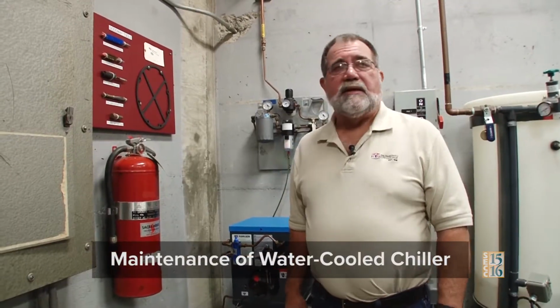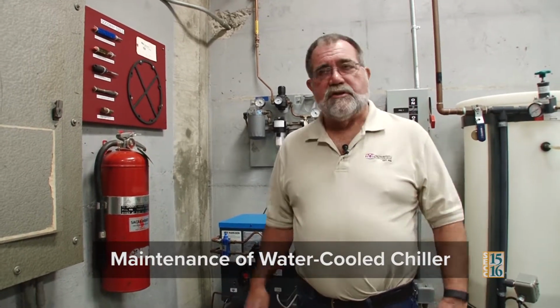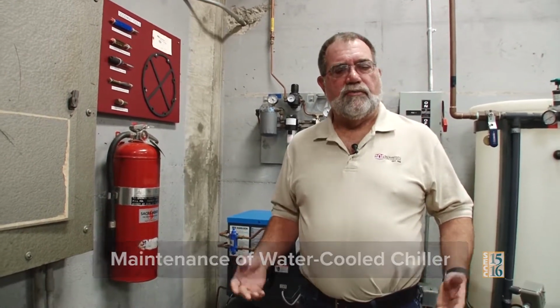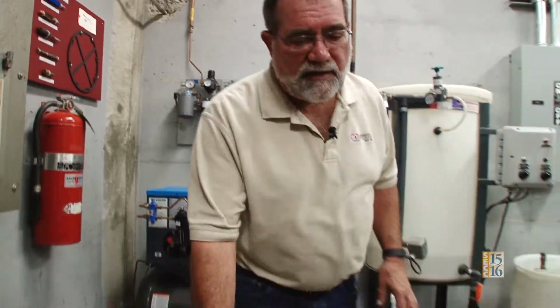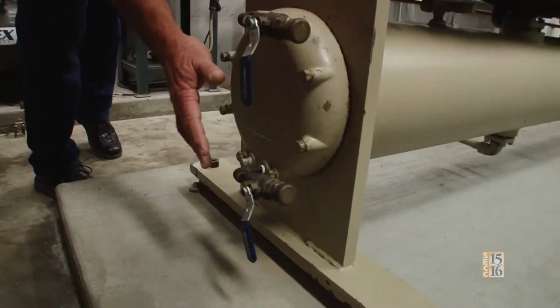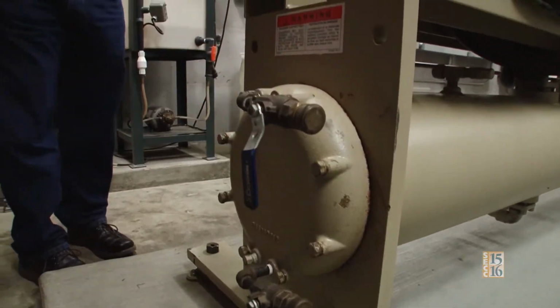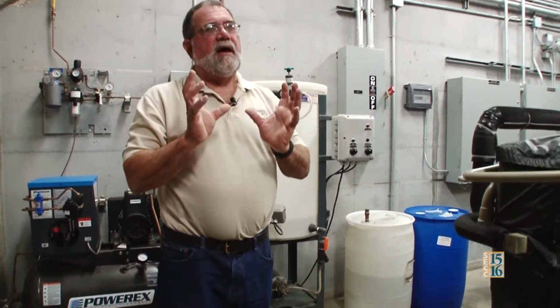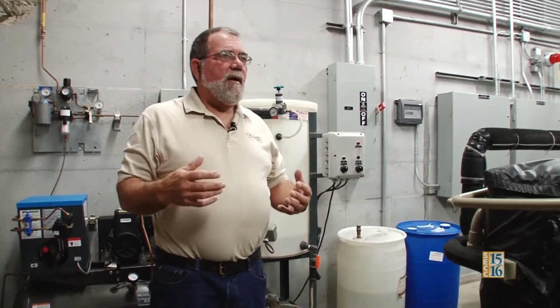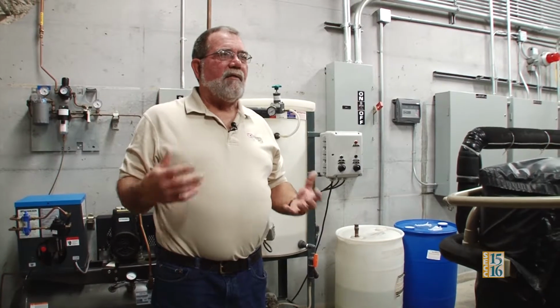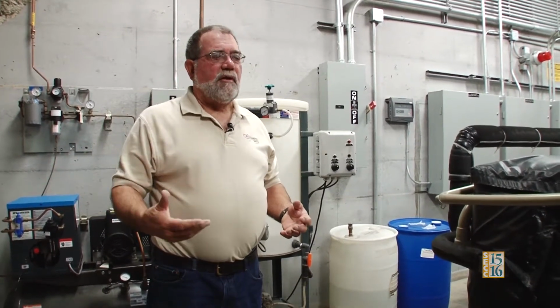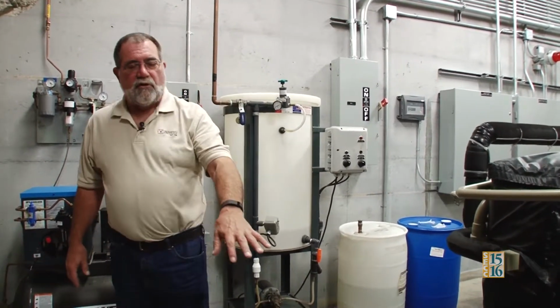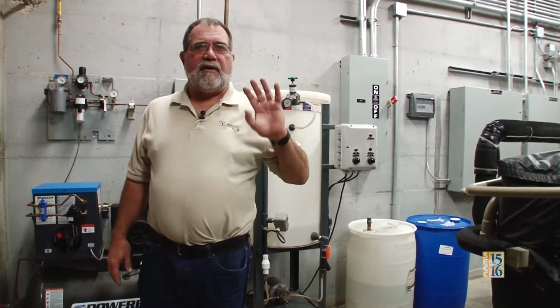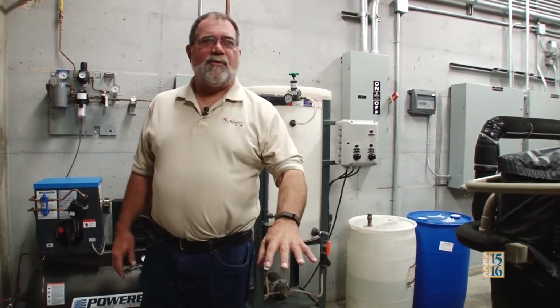One of the maintenance tasks on water-cooled chillers is what we call punching tubes — inside this condenser barrel we have water running through tubes and refrigerant on the outside, so we clean the tubes to get good heat transfer. We clean our tubes twice a year, because I have a class twice a year, and that's what we do.